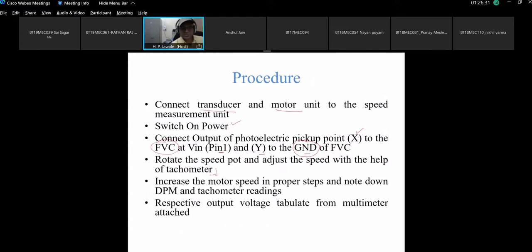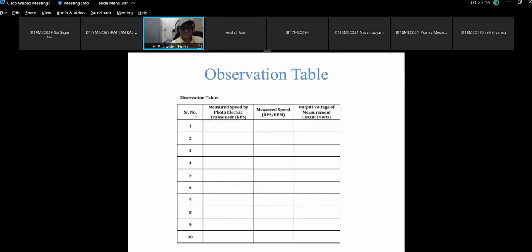Then increase the motor speed in proper steps, whatever is shown in the display. Suppose now I am going to take the speed in RPM. With the given steps, 5 RPM, 10 RPM, 15 RPM and so on, we increment the speed in steps and note down the display panel reading as well as the tachometer reading for the given speed. Then the respective voltage output is also noted down from the voltmeter and tabulated in the observation table. So the observation table: measure speed by photoelectric transducer.